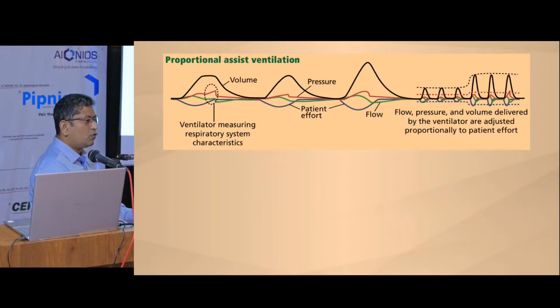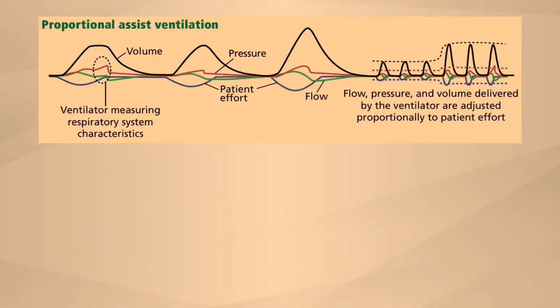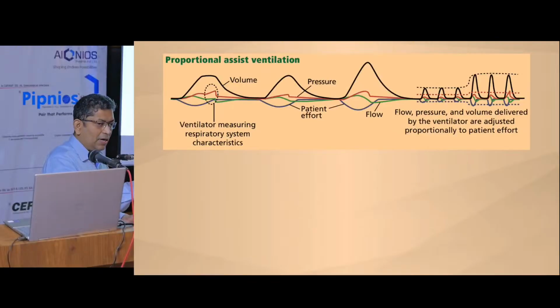Okay, it measures the effort through the airflow actually. Once the ventilator knows the compliance and resistance, looking at the flow, you can figure out the patient's work of breathing. And once it gets the work of breathing, a percentage of that, which you have to set, 10%, 100%, whatever it is, the ventilator will give extra. If you give 100%, whatever the work of breathing is, the ventilator also gives double that, totally double. So more air will basically come.